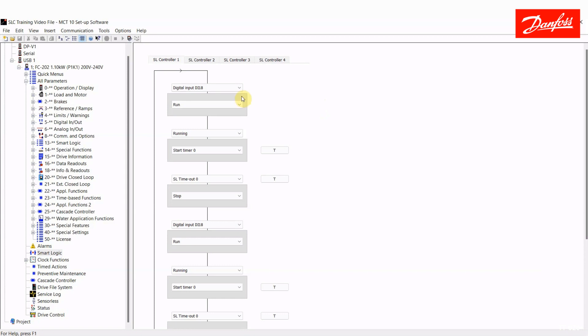So I'm waiting here for my first event to become true and someone presses the button wired to digital input 18. That's the open button. Once someone presses that button, the drive will run and I drop down to my next event. I have chose for that event running. So I know that is true because I just told the drive to run.